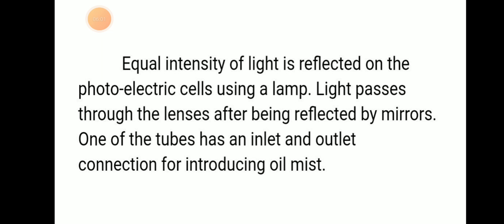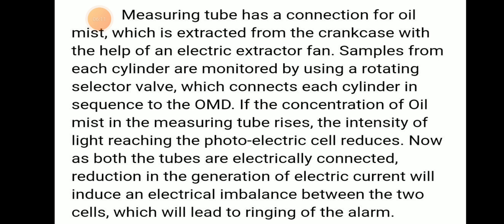One of the tubes, the measuring tube, has the inlet and outlet connection for introducing oil mist, because it measures the oil mist extracted from the crankcase with the help of an electric extraction fan.